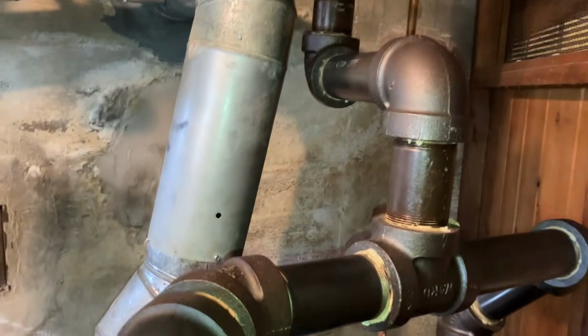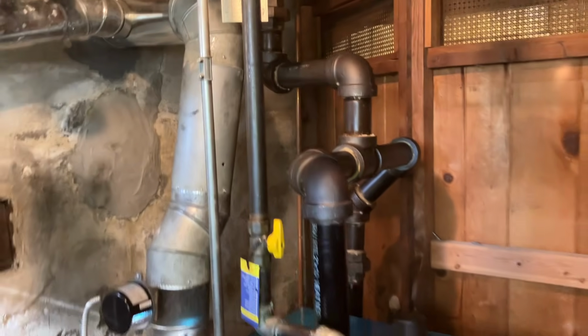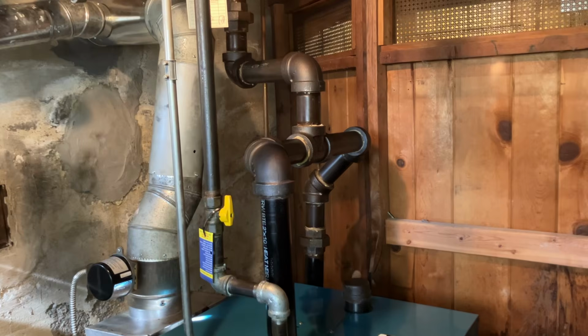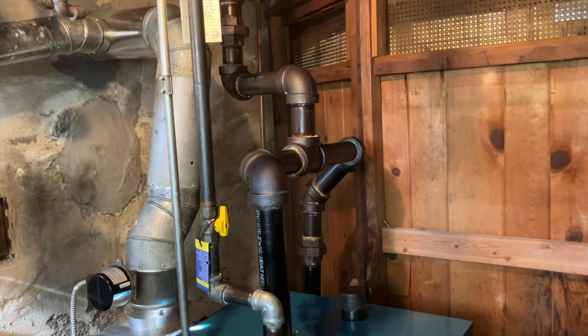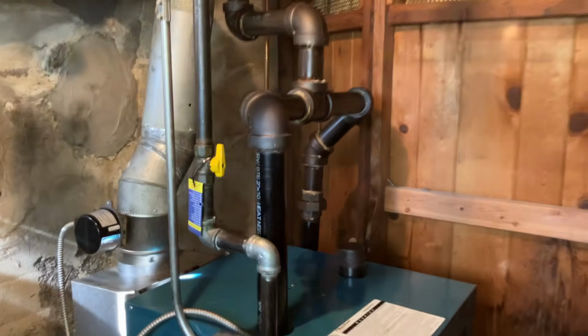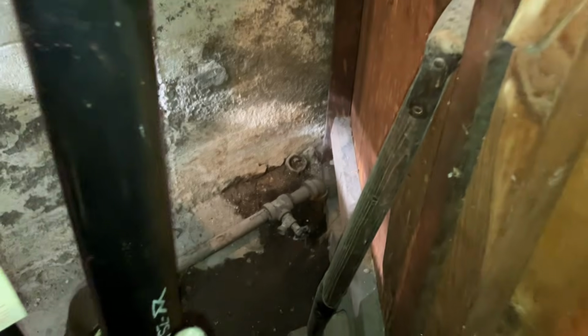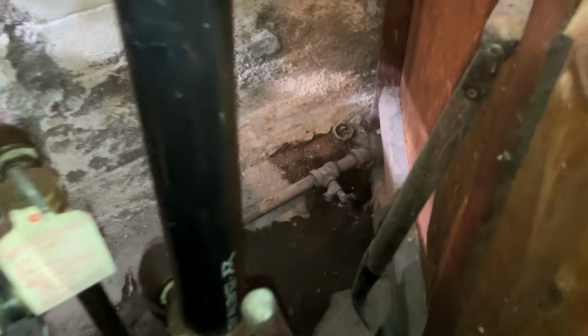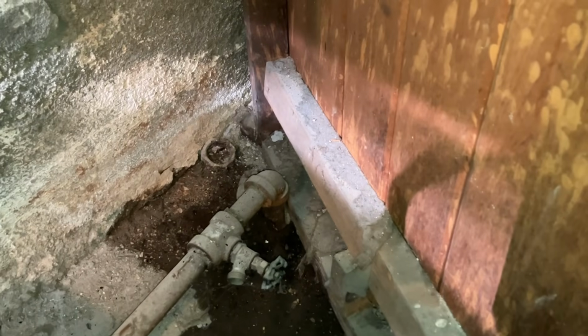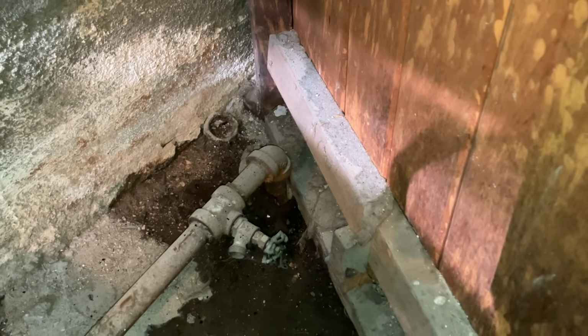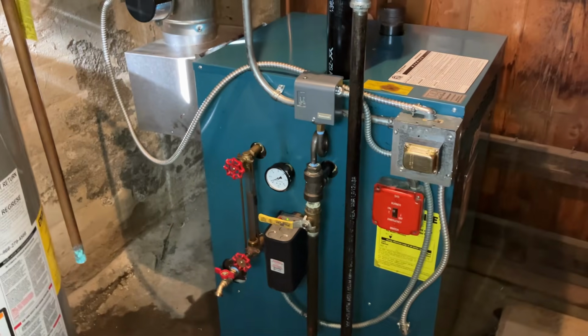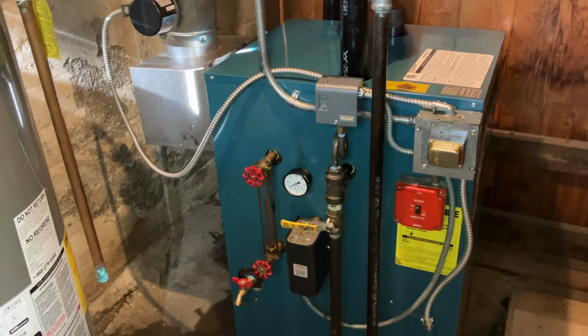But guys, if you're working on steam systems or any hot water heating system, it's to everyone's benefit to insulate the piping, and especially the condensate return. Insulate that as well. And that one is an underground return. Look at that, it goes underground. So that could be a possible point of water loss, and that could be explaining why the homeowner is adding water to the boiler every 3 days.